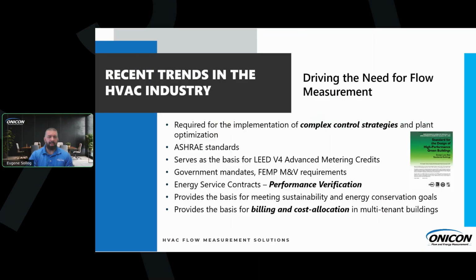Certain trends that we're seeing are driving the need for flow measurement. You can break this slide down to three basic points: measuring, controlling, and billing. Measuring is just getting a flow meter in, seeing what's happening in your system, what's going where, what your loads possibly are. Controlling is staging chillers, staging boilers, etc., trying to get those control strategies to get an efficient energy plant. And then billing is another big one that we're seeing more often, and this is even down to the tenant level. You could have individual tenants and put a flow meter or BTU meter on each one of these, and bill based off of actual usage on the BTU side.